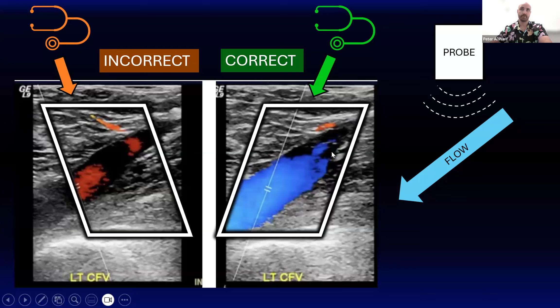We've got two examples here. This is an artery that's flowing in this direction. Because the steering is angled this way, the machine thinks the blood is moving towards the probe. In this case, we've got the steering pointing in this direction, and the machine's accurately picking up the flow moving in that direction. Remember, blue away, red towards. So what we want to do is get that steering angle in line with the direction of the flow as much as possible, and that'll give you the best interpretation of what the flow is doing.